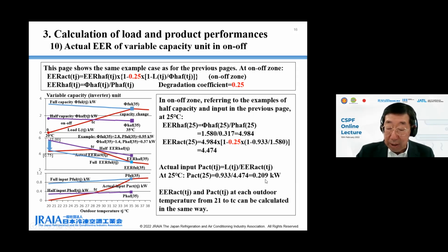ISO T1 bin hours exist from 21 to 35 degrees C. Actual EER and actual input at each TJ in the on-off zone, from 21 degrees C to the cross temperature TC, can be calculated in the same way, which is from 21 to 28 degrees C in this example. In order to calculate actual EER of a variable capacity unit in the on-off zone, 35 degrees C half capacity and EER data are required, as well as 35 degrees C full capacity and EER data.